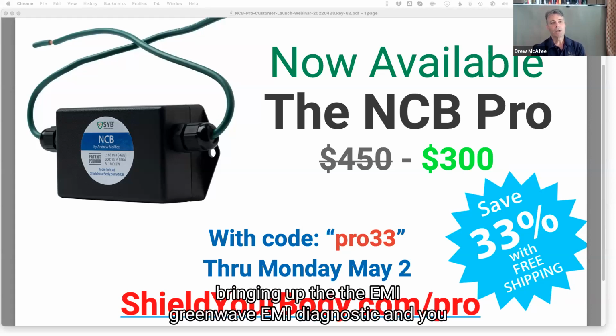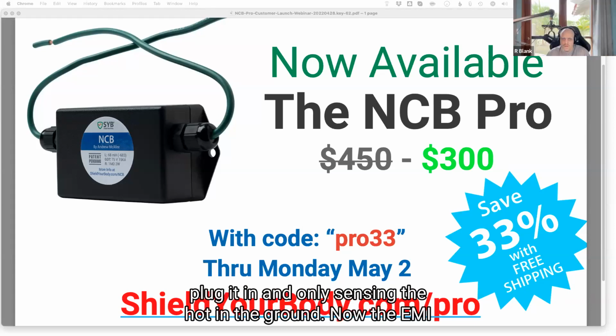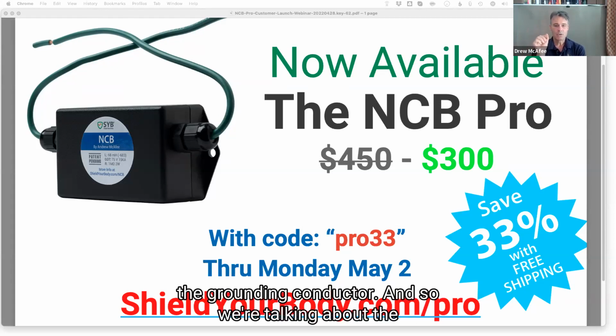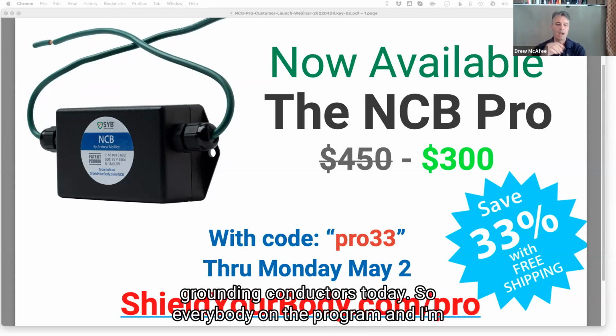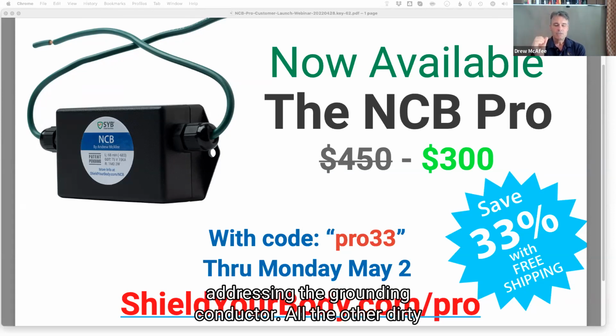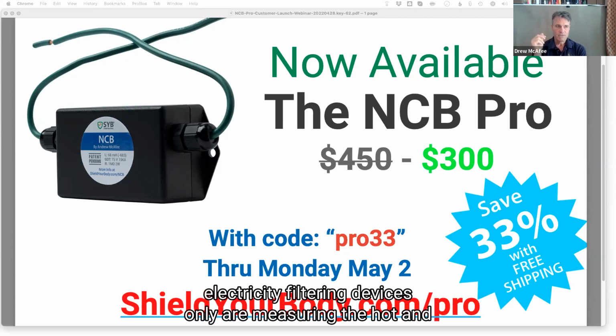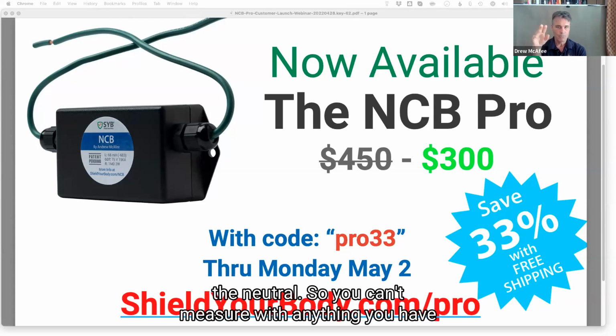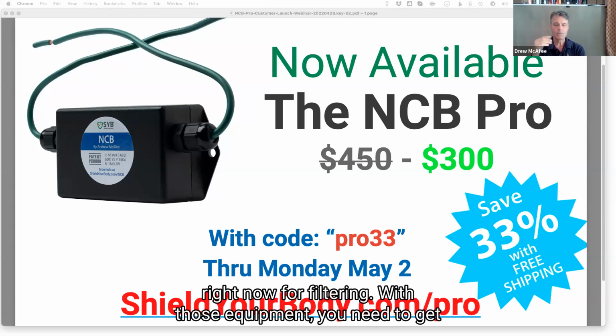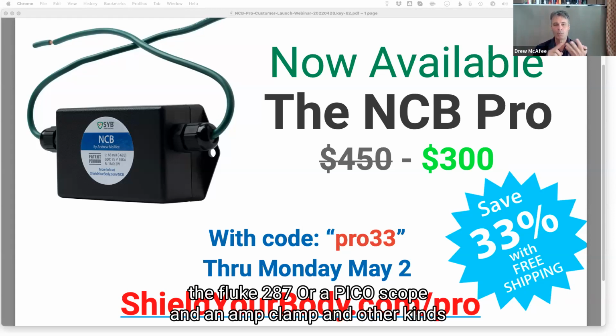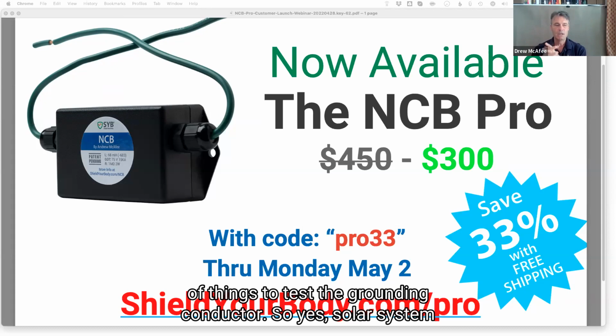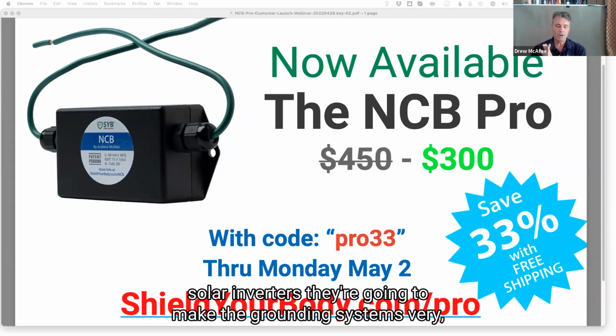That's a really good question. Thank you for bringing up the EMI green wave diagnostic. You plug it in and it only senses the hot and the neutral. The EMI or Stetzerizer dirty electricity meters do not sense the grounding conductor - we're talking about grounding conductors today. So for everyone on the call, and I'm glad there are still 80 people on today, this only addresses the grounding conductor. All the other dirty electricity filtering devices only measure the hot and neutral, so you can't measure what you have now for filtering with that equipment. You need a Fluke 287 or a picoscope and an amp clamp to test the grounding conductor. So yes, solar inverters will make the grounding system very noisy.